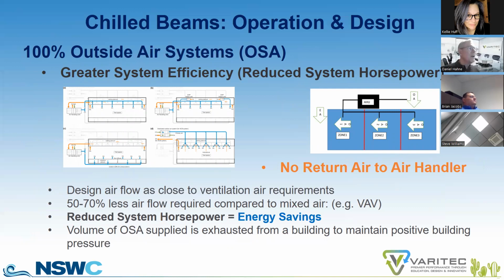So again, 100% outside air systems. If we decouple the sensible from the latent load, we allow the outside air to be provided at a condition that will handle building latent cooling. We can result in systems that are of greater efficiency.